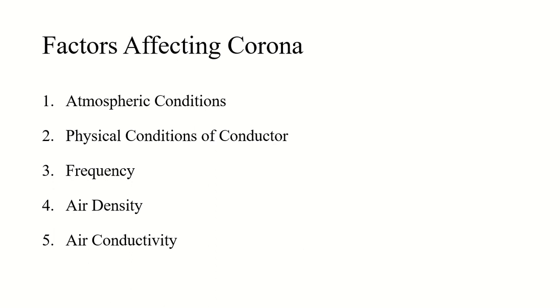Except for that, we have more factors which affect corona. Another one is the frequency. We earlier saw that corona is directly proportional to the system frequency. Another one is the air density. So we saw that corona is inversely proportional to the air density.